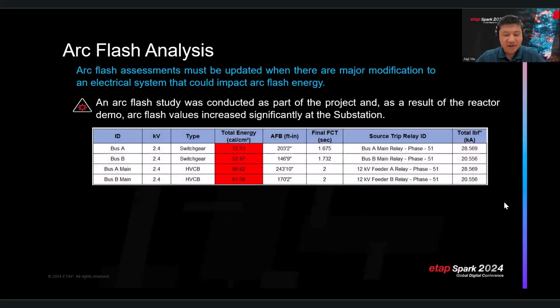So with a system modification like this, we know that your arc flash assessment needs to be updated for any potential arc flash result change. We run the arc flash, so I put a table here to summarize the results. You can see that for the substation 2 bus A and bus B, and the 2 main breakers, they all got a very high incident energy. This is first due to a very high fault current because of the removal of the line reactors.